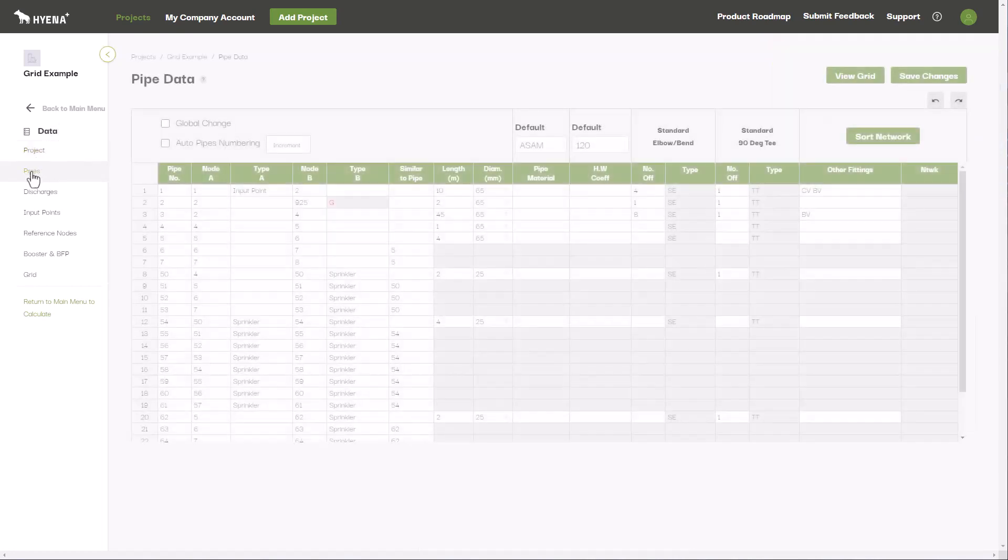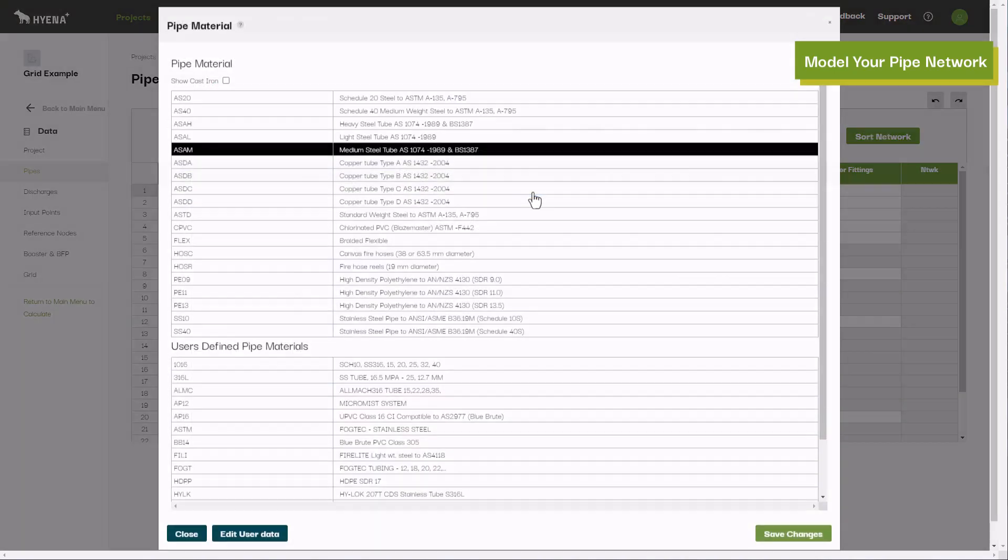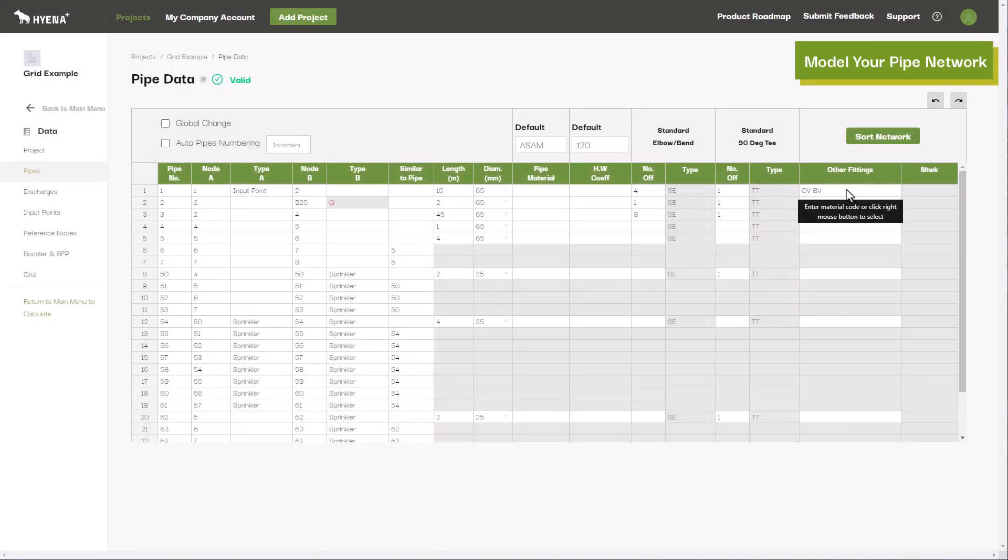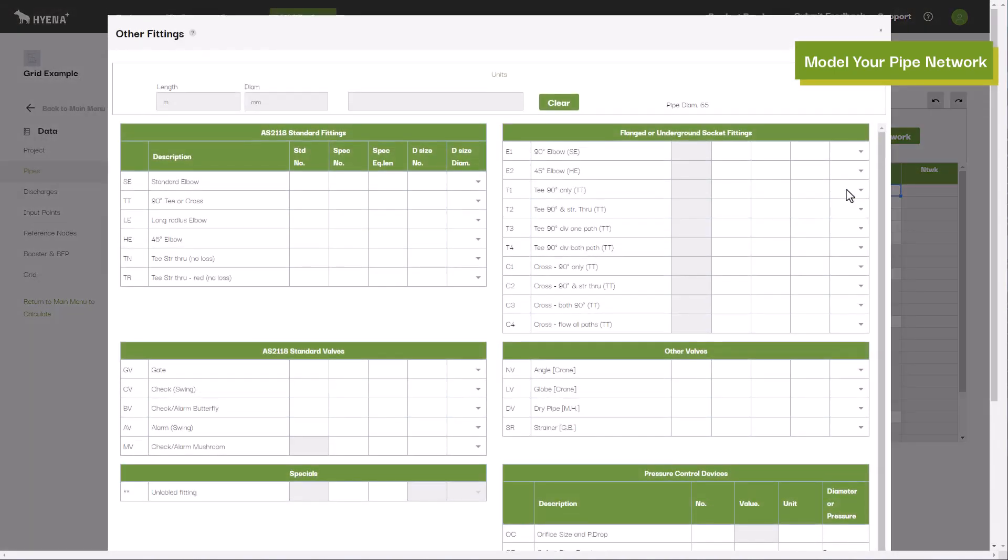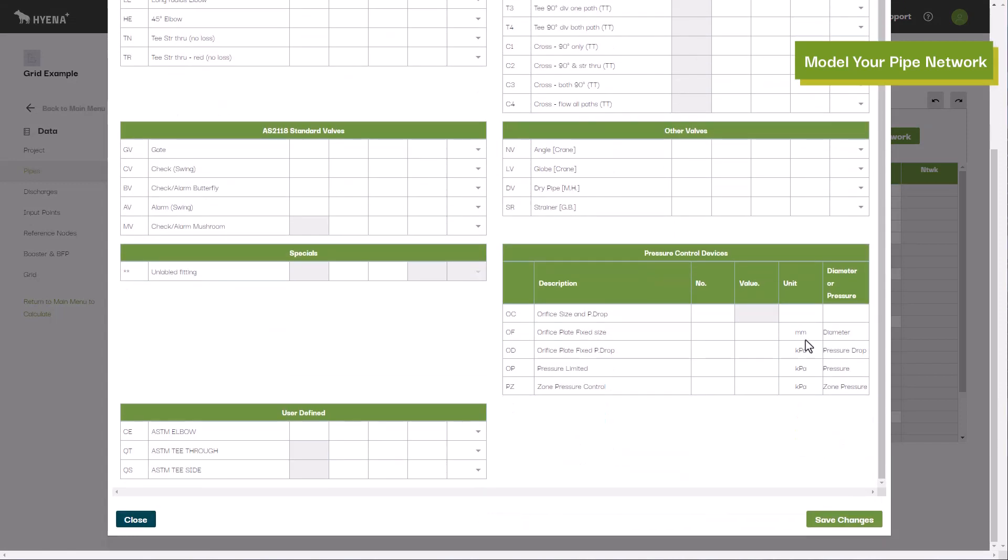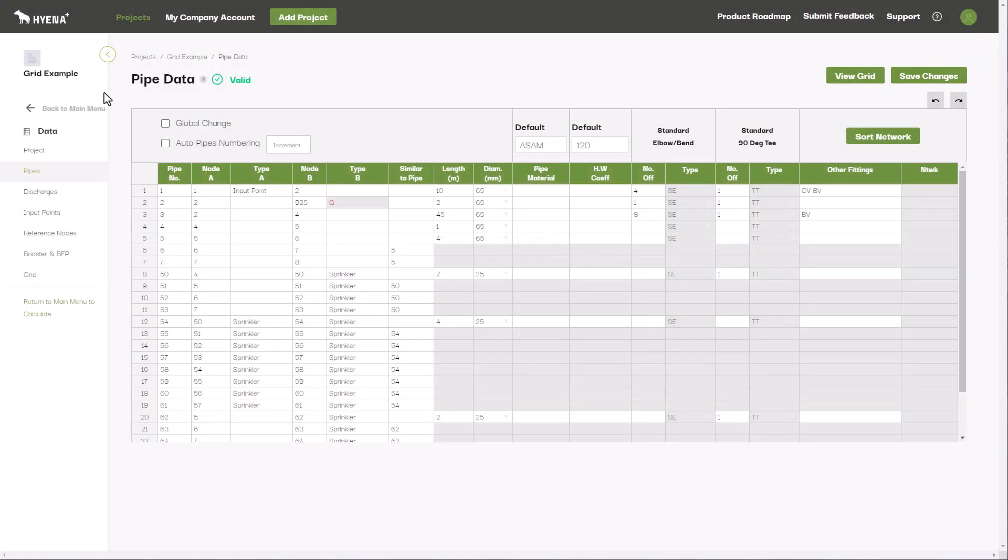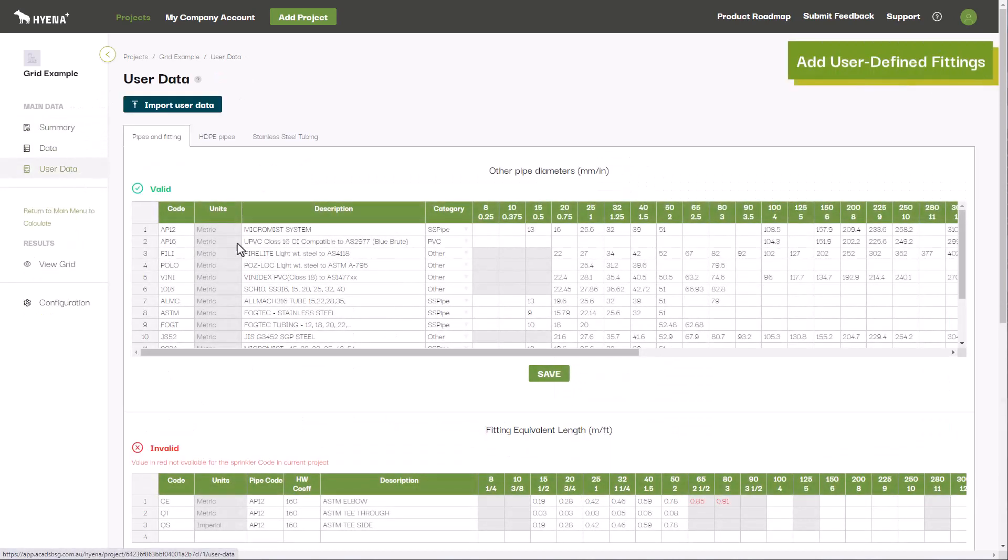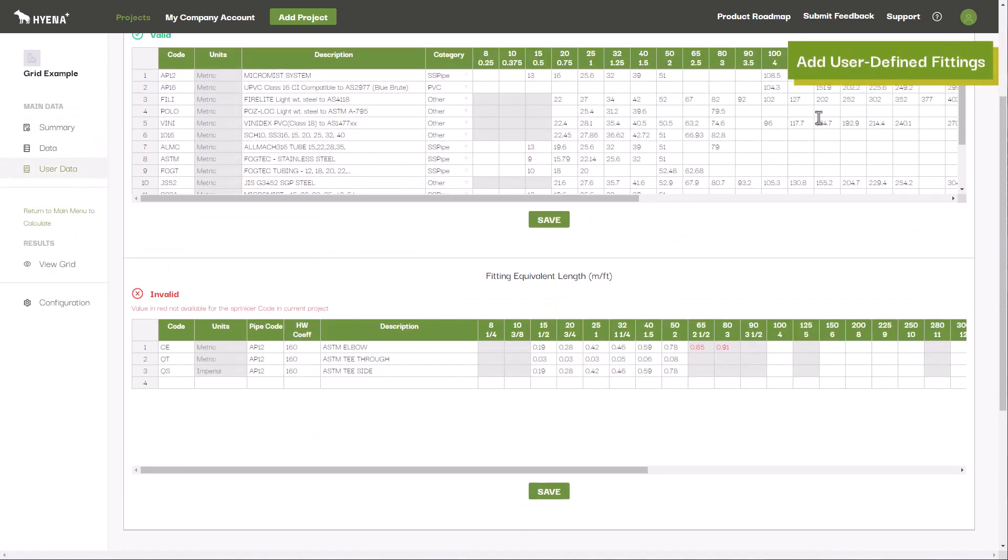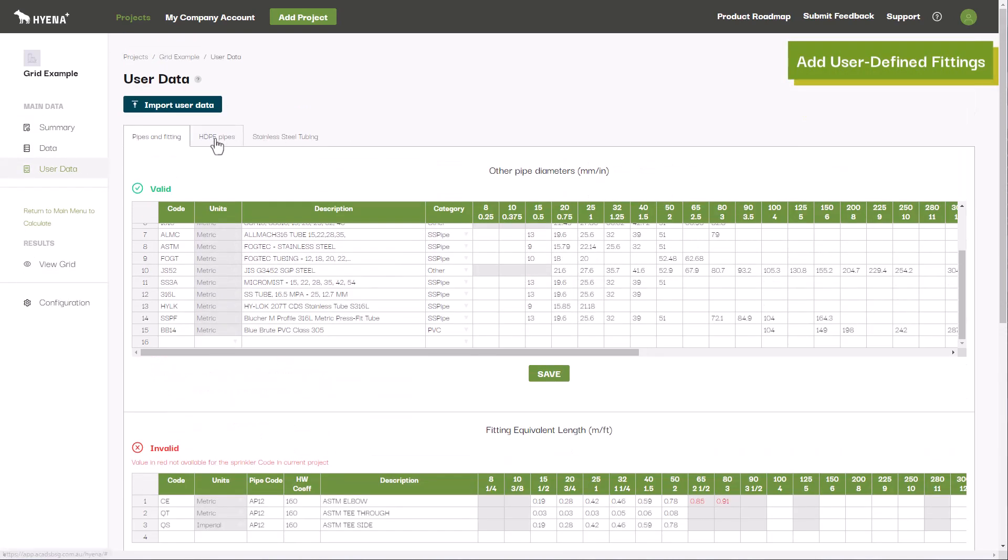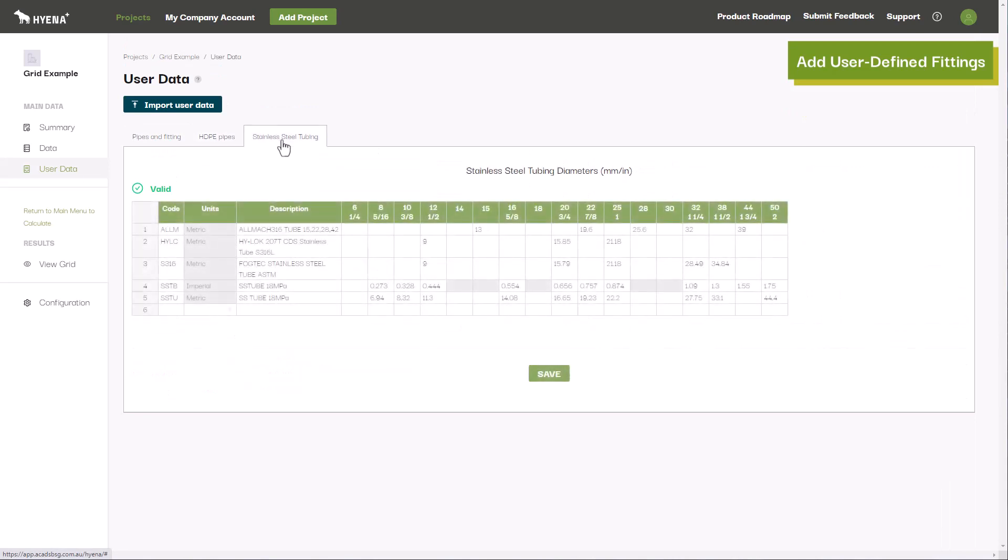Hyena Plus allows you to enter in your pipe network from node to node, specifying the pipe lengths, diameters, materials, and any elbows or fittings in the network. A wide range of fittings are provided with the equivalent length stored in the program for the various standards. Users can add to this with their own custom fittings and associated equivalent lengths, typically sourced from manufacturer data sheets.